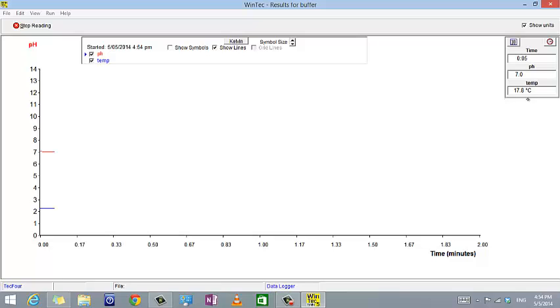If you're worried about the calibration of the temperature, you can put in a thermometer and measure that temperature initially and then do the set 0 or set value, just like you did for the pH. What I'm going to do now is add a little bit of hydroxide, just to change the pH a little. So that changes a little bit because we've got a buffer, and it should come to some new equilibrium. And it's changing a little bit more.